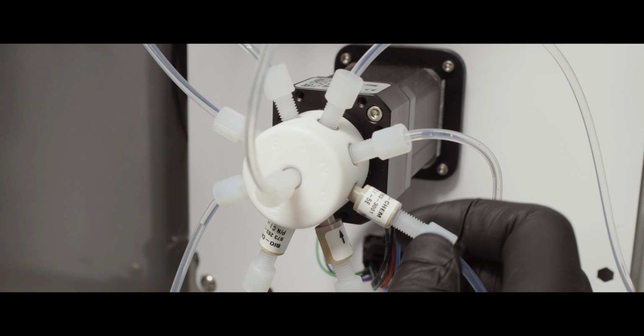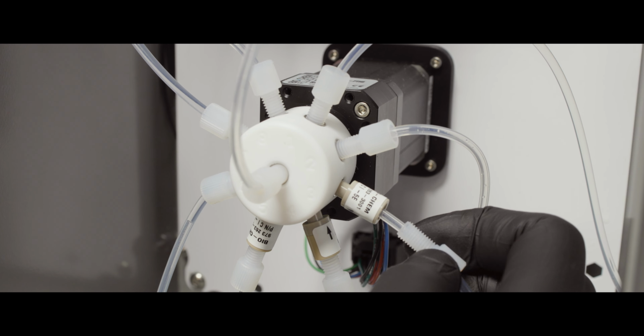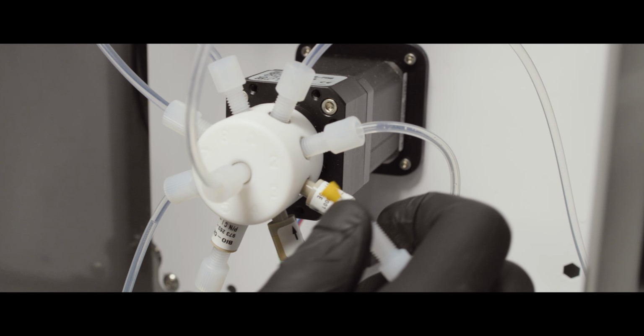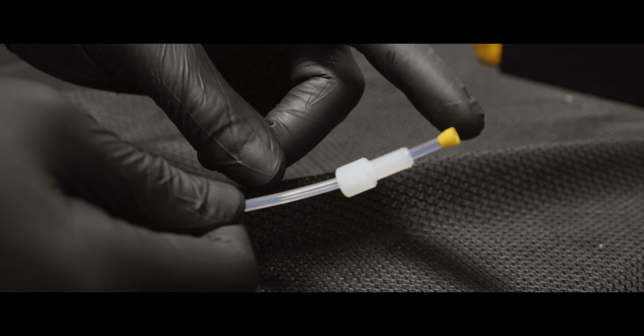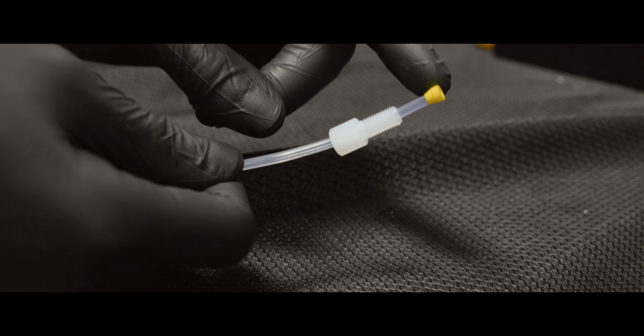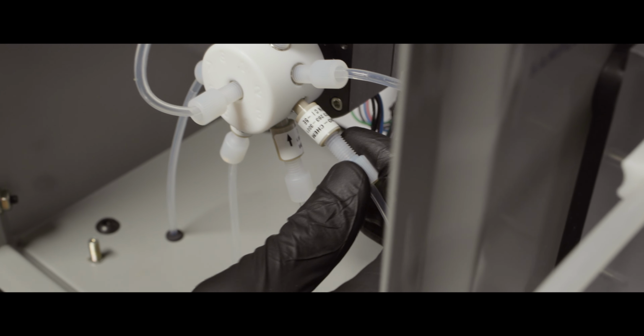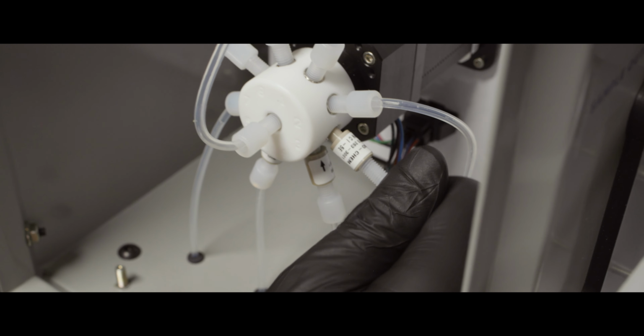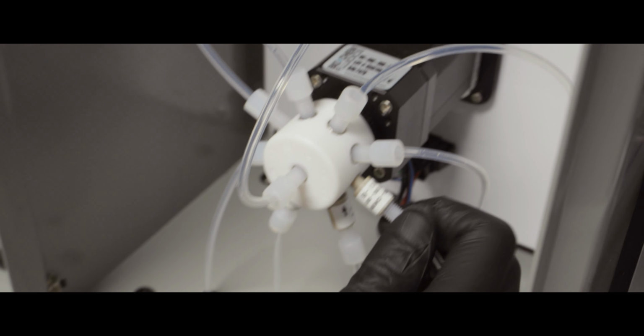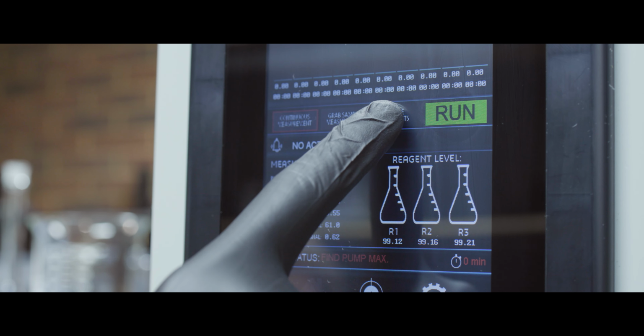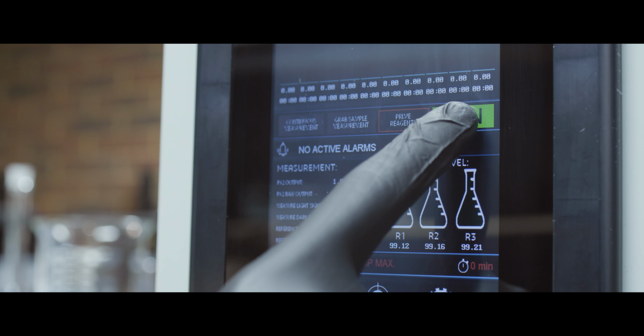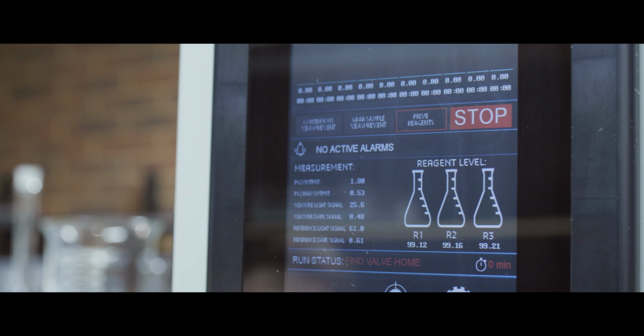Step number 2, press stop and wait for the idle message to appear on the display. Step number 3, disconnect the tubing by unscrewing the fittings while taking extreme caution to avoid any liquid spills from any remaining reagents. Ensure to keep track of all the yellow ferrules. Step number 4, replace all tubing with tubing from your RS1 maintenance kit. And step number 5, once your tubing is replaced, press prime reagents on the Narwhal display.